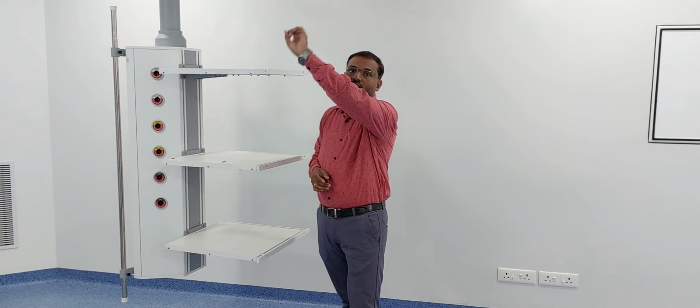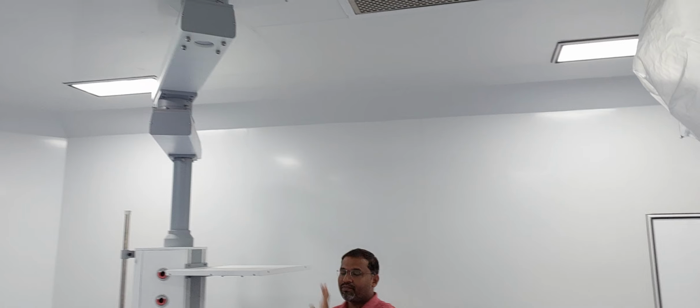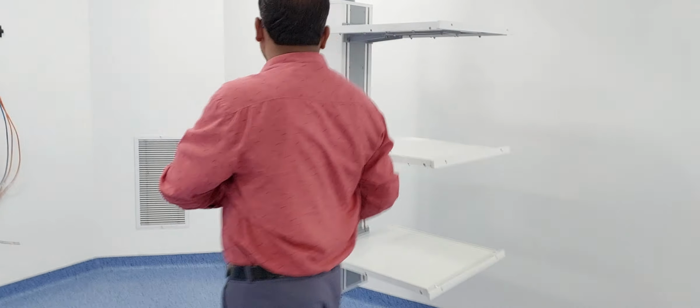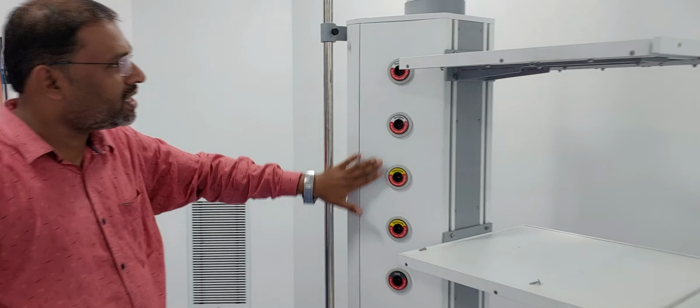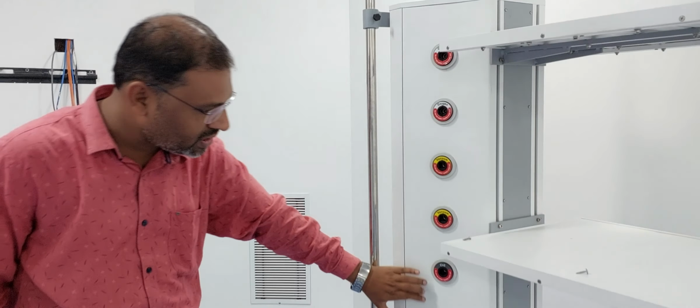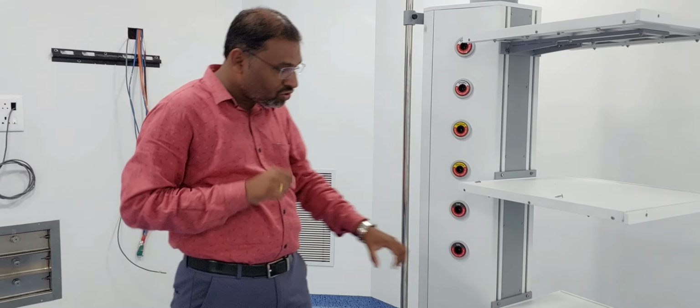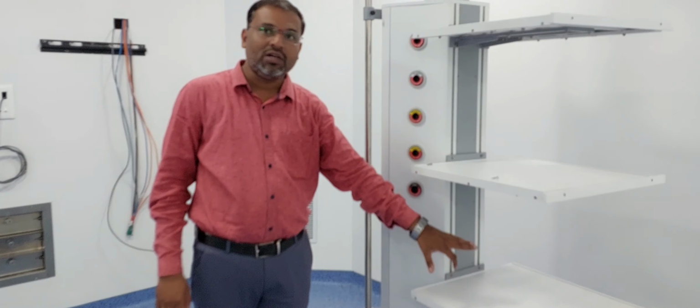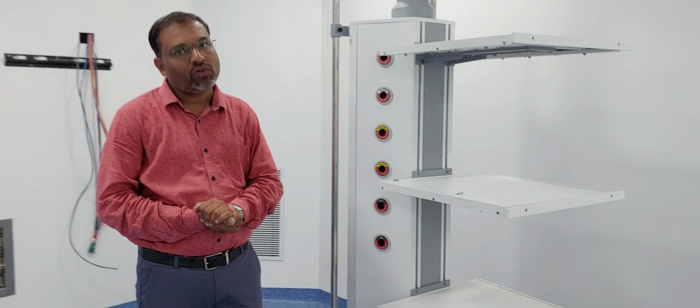Once it gets connected, we will attach it to the surgical pendant. For standby purposes, we have given gas outlets on the surgical pendant also. These are 2 oxygens, 2 vacuums, and CO2. If you are going to put CO2 separately on the surgical pendant, you can give CO2 input to the CO2 insufflator.